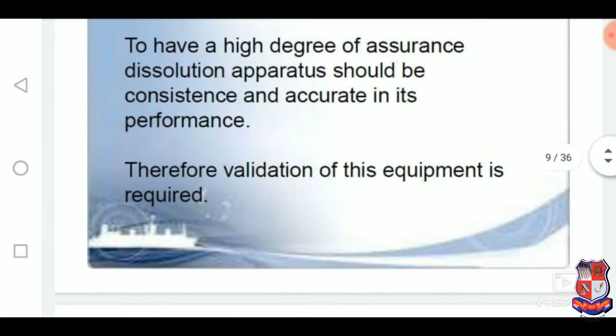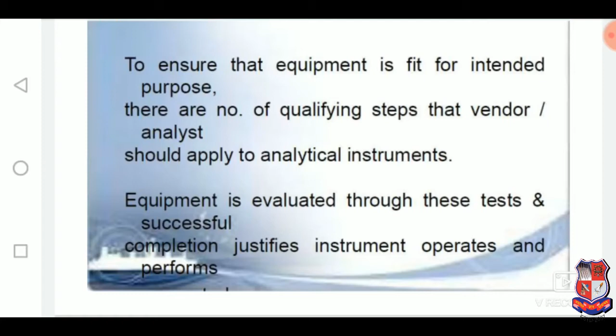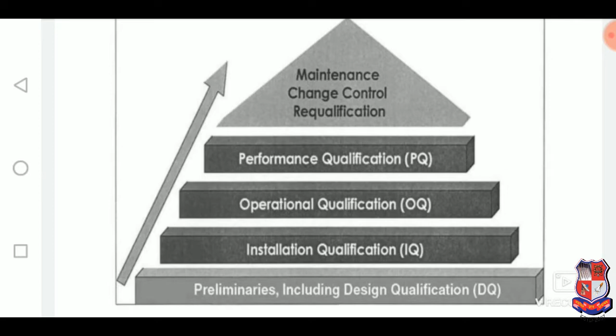And qualification is a part of validation, and it is done to ensure that equipment is fit for its intended purpose. There are a number of qualifying steps that vendors and analysts apply to analytical instruments. Equipment is evaluated through these stages, and successful completion justifies instrument operation and performance. So these are the qualification subparts: preliminary steps include design qualification, installation qualification, operation qualification, performance qualification, and at last maintenance, change control, and requalification.